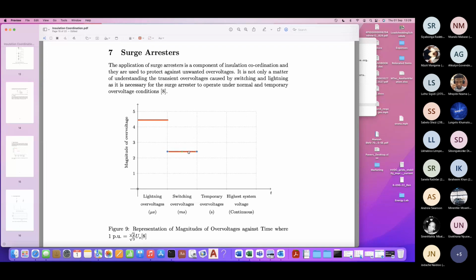Our switching voltages are much, much smaller. They sit around 2.5 per unit, but they are of a much longer duration. Temporary overvoltages occur. Those are due to switching on a line or just generators going too high. And finally, your highest operating voltage is just above 1.